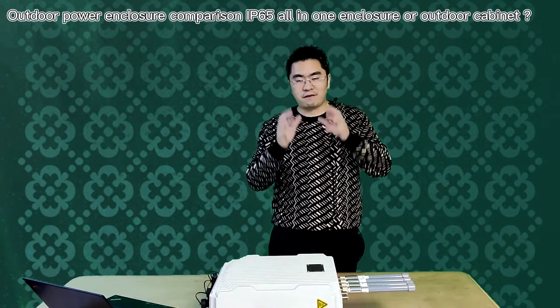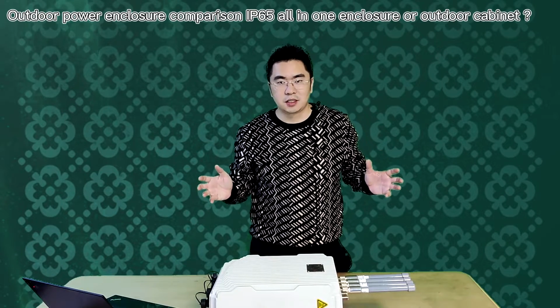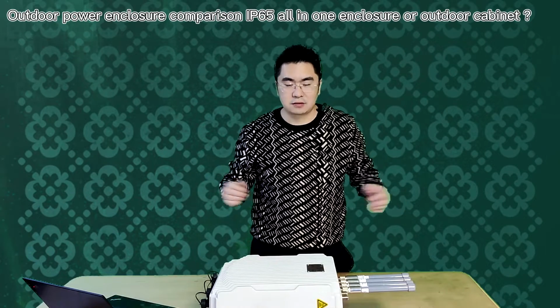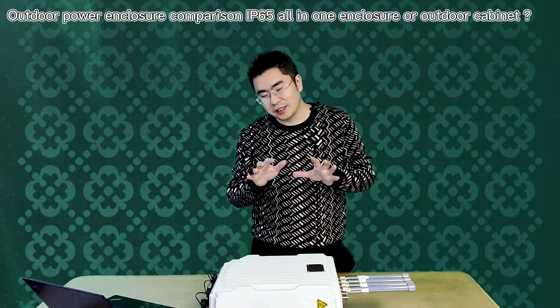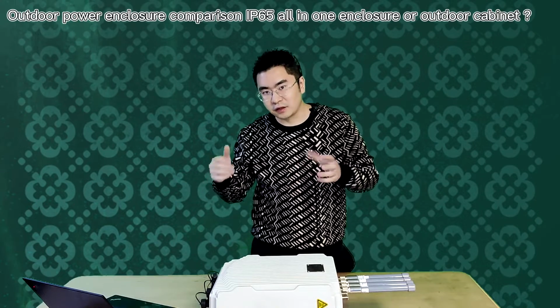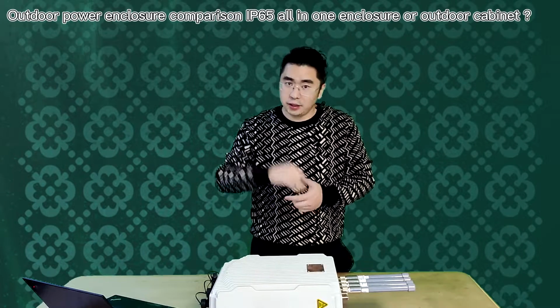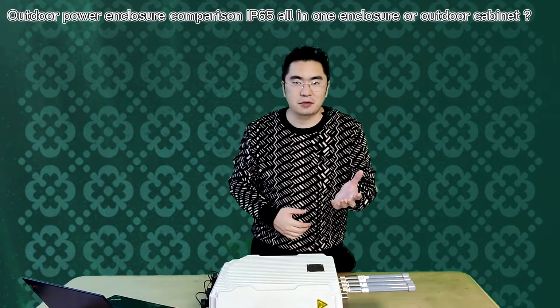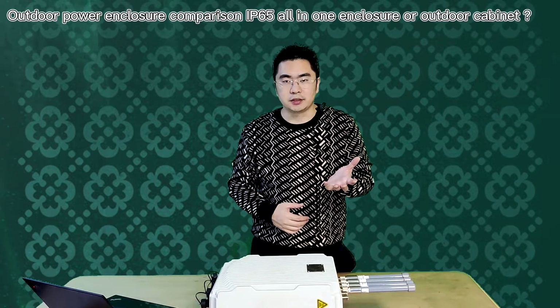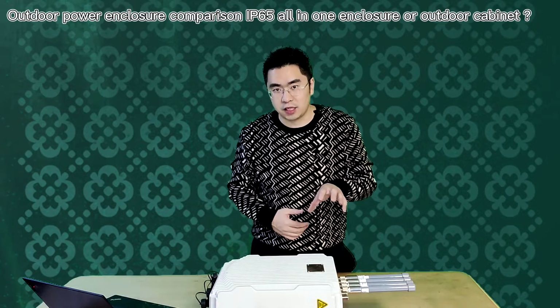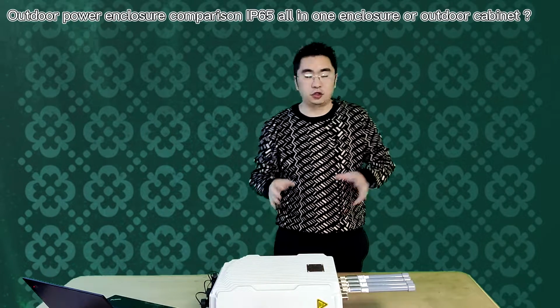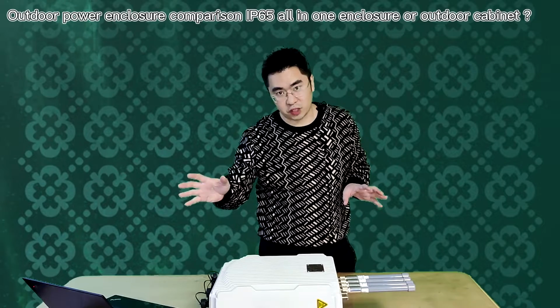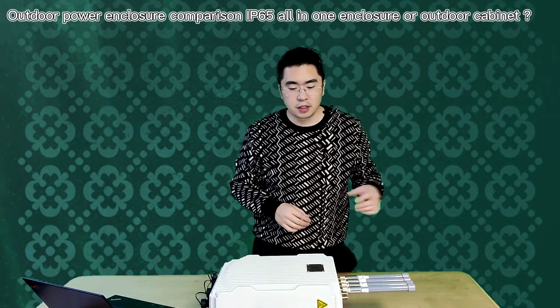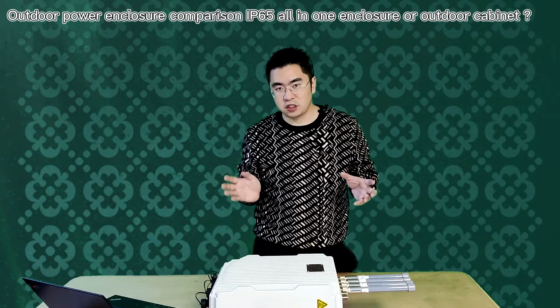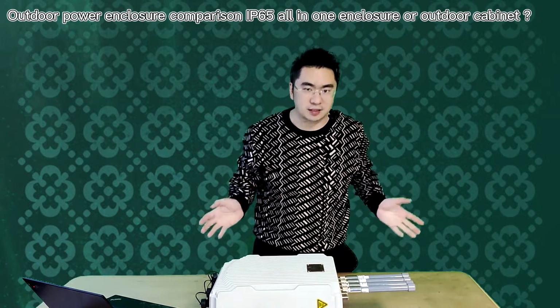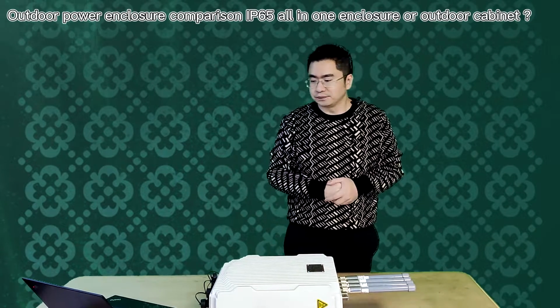But think about it. If you have a massive deployment and a lot of sites, and your battery lifetime is harmed by this kind of wrong installation. On the other hand, because your lead acid battery has no monitoring of the battery life, in the end, 2 or 3 years later, you don't really know which sites your battery is okay, or which sites your battery is broken. So you have to send an engineer for a site survey. With so many sites, what's the operation cost, right?